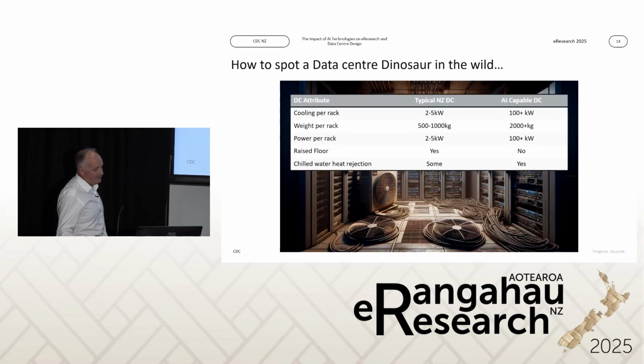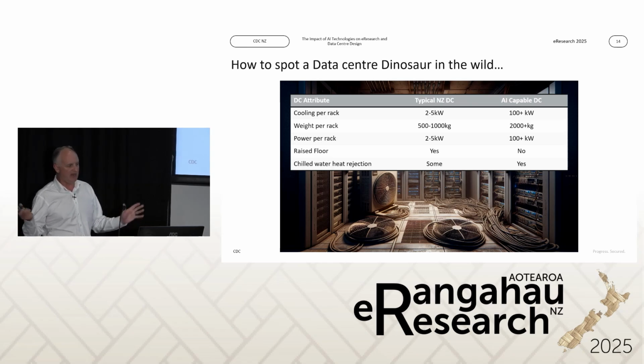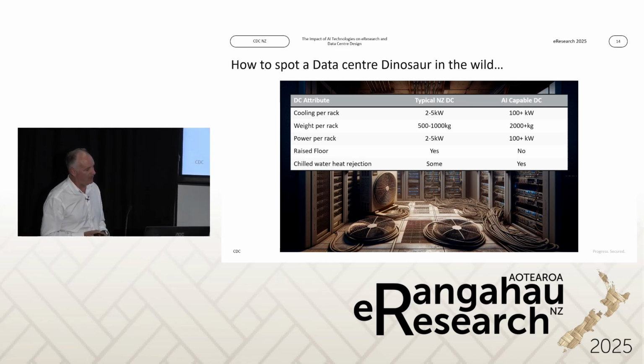Breaking that down, what does it mean? If you look at an average New Zealand data center, they've been designed to 2 to 5 kilowatts a rack, designed for weights in the vicinity of 500 to maybe 1,000 kilos. Raised floors have been used, and some data centers do have chilled water heat rejection, but a lot don't. A modern AI-capable data center, we're talking 100 plus kilowatts a rack, 2-ton racks, no raised floor because the racks are way too heavy to do anything with a raised floor, and you must have this chilled water heat rejection.